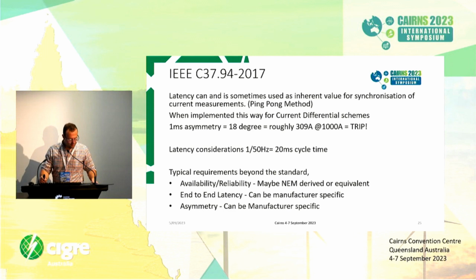Again, as touched on by James, the ping pong timing method can be used by protection equipment, and it uses half of that round trip delay to offset the comparison of current vectors. Unless, as he said, interlocked or qualified with additional fault indicators, asymmetry in the telecommunications channel can result in maloperation of the protection scheme.